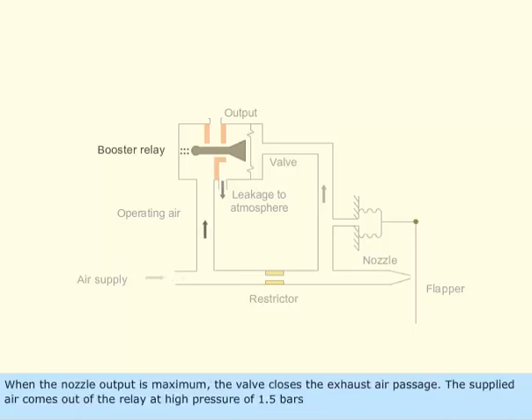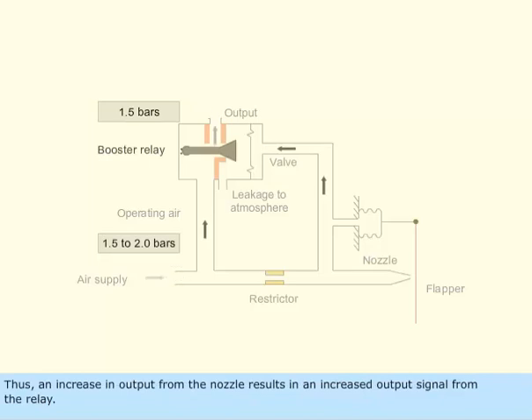When the nozzle output is maximum, the valve closes the exhaust air passage. The supplied air comes out of the relay at high pressure of 1.5 bars. Thus, an increase in output from the nozzle results in an increased output signal from the relay.